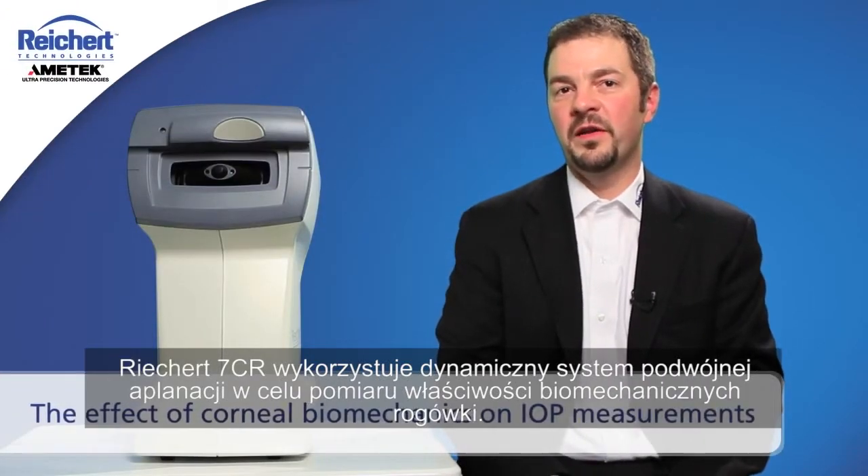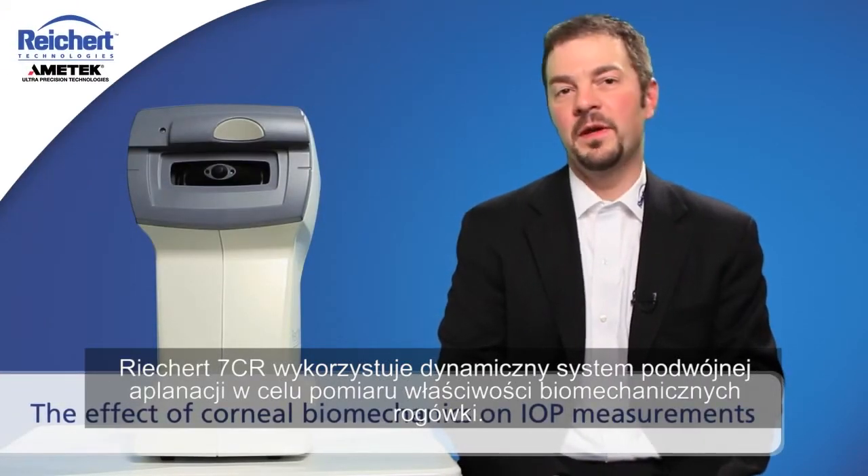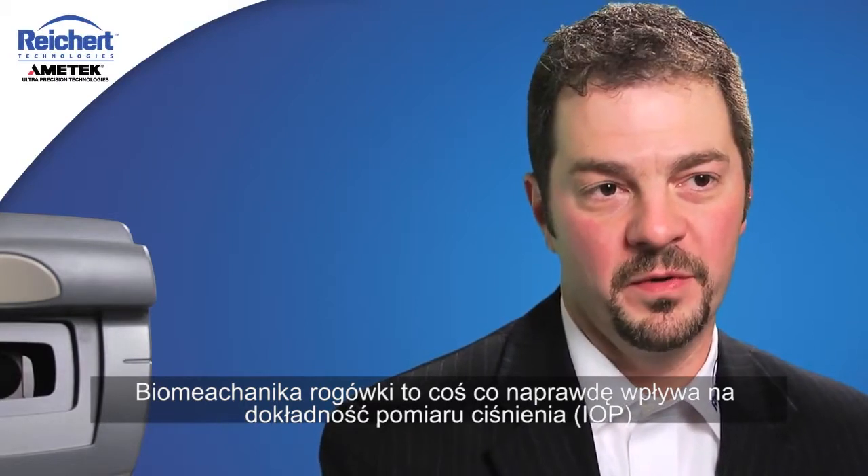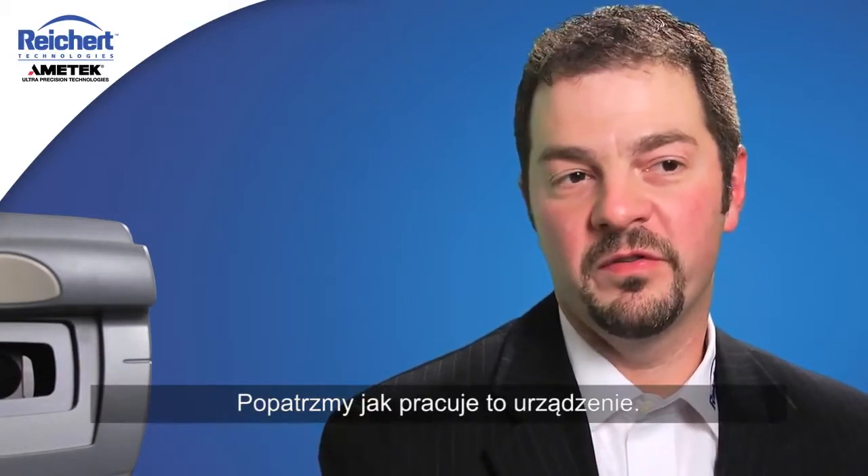The Reichert 7CR utilizes a dynamic bi-directional applanation system to quantify the biomechanical properties of the cornea. Corneal biomechanics is really what influences the accuracy of tonometry measurements. Let's take a look at how the system works.